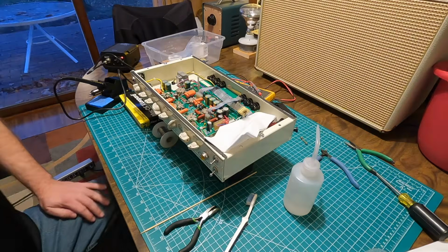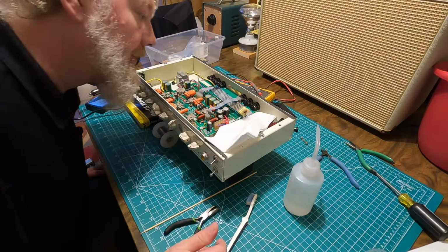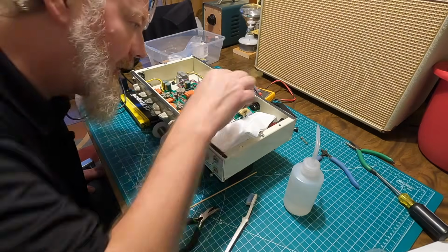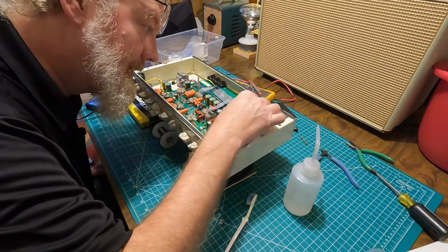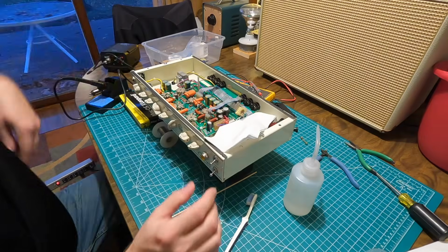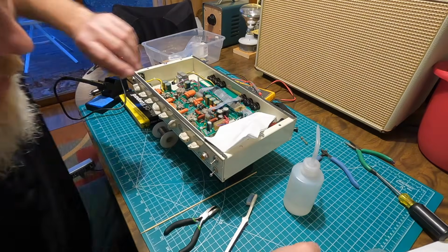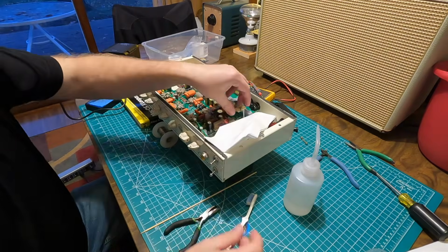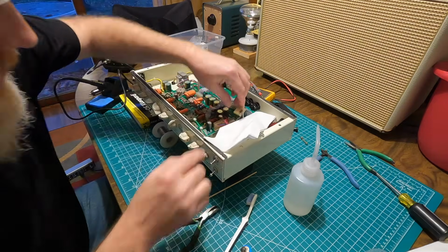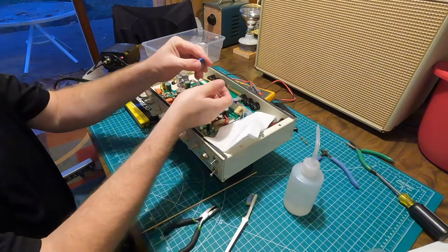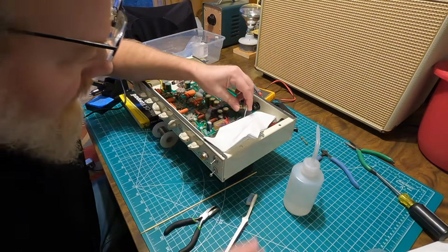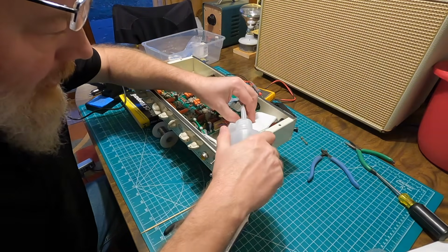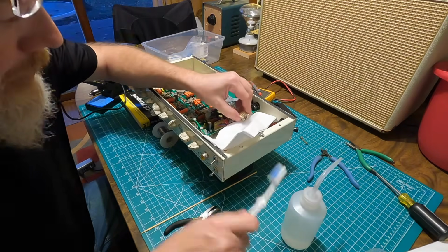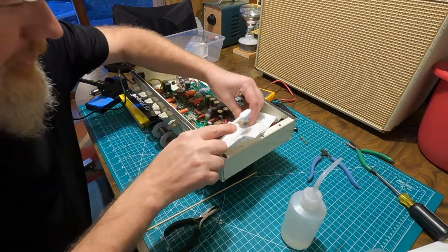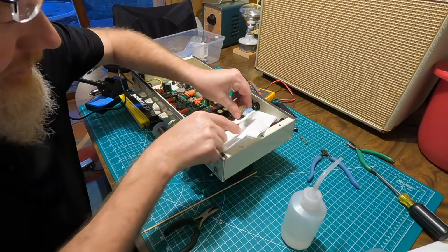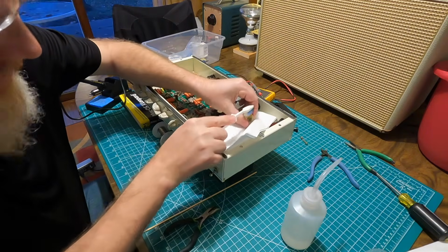Well, luckily here, I've been doing some continuity checks, and all the wires are good and all the connectors are good. So while this arced and blew up, I think this brown discoloration is from the arc flash that came out of the MOV. But just to be sure, I'm cleaning it with an alcohol wipe, isopropyl alcohol and a toothbrush, to make sure all the connectors are clean and dry.